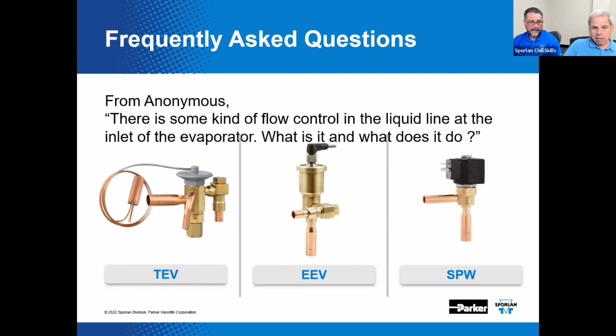There's another thing it could be: an SPW, or Sporlan pulse width valve. This is also technically an EEV, but it operates on the same principle as a solenoid valve. It can also control superheat in this application, and it provides pulse width operation. So instead of stepping partially open and closed like a stepper EEV, it is either fully open or fully closed, but in very small time slices.